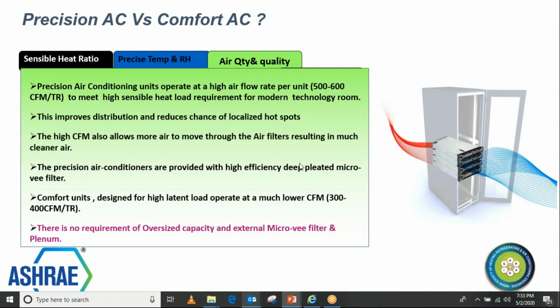So the CFM per TR in precision AC moves from 500 to 600. Even in some cases it goes up to 650, and obviously it depends on what type of application it is. There are some applications which demand slightly lower CFM per TR, because the equipment has a higher delta T also. So when you have higher delta T, CFM per kilowatt slightly comes down, but then your return air temperature to the cooling unit goes up. So these are also important points to note.